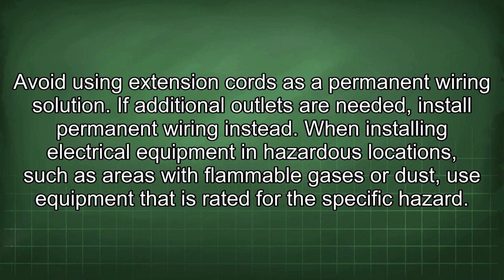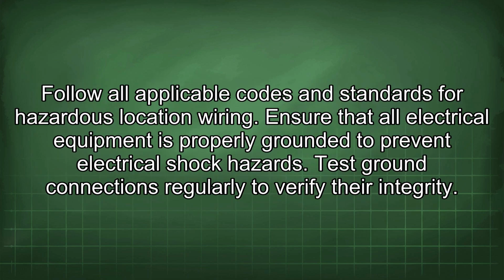When installing electrical equipment in hazardous locations, such as areas with flammable gases or dust, use equipment that is rated for the specific hazard. Follow all applicable codes and standards for hazardous location wiring. Ensure that all electrical equipment is properly grounded to prevent electrical shock hazards. Test ground connections regularly to verify their integrity.